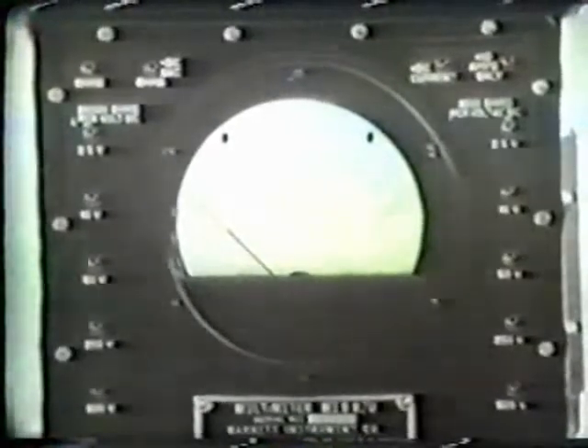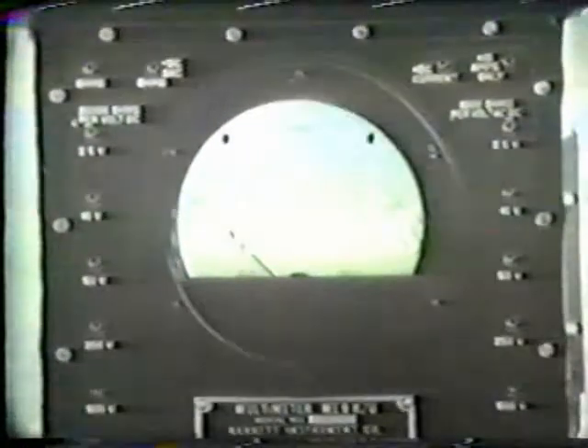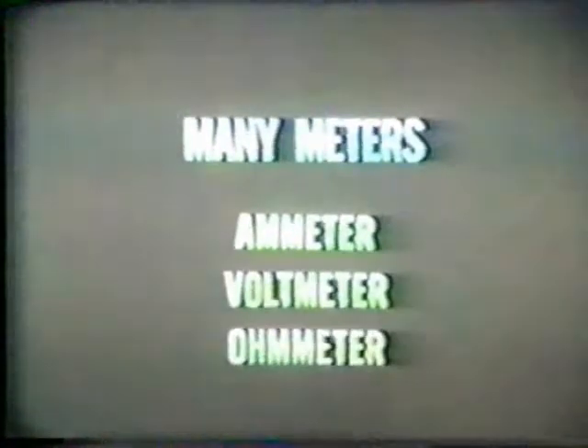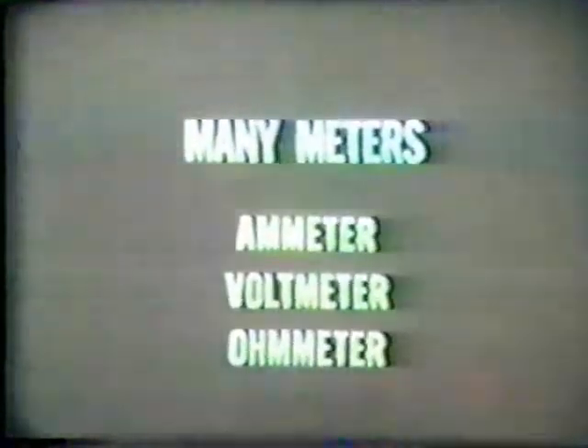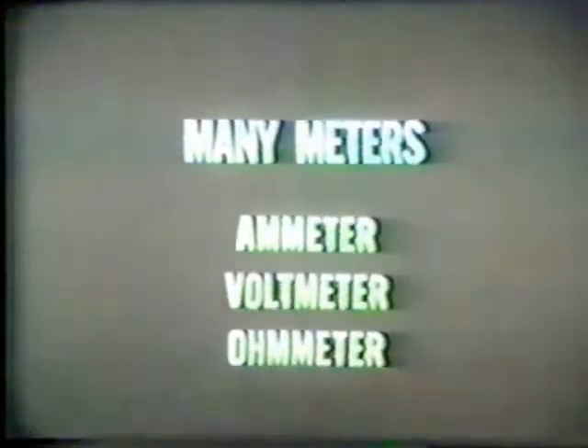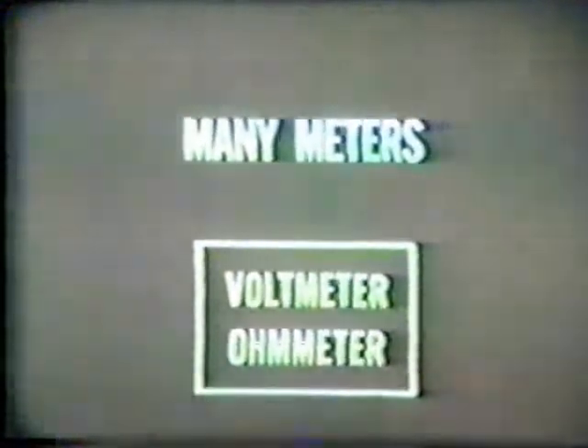A multimeter can do everything a jumper wire and test light can, as well as providing the extra sensitivity required for some electronic and instrument circuit testing. A multimeter looks quite complicated, but it is not difficult to learn to use one. Multi means many, and a multimeter is actually many meters in one. The multimeter which you will be using contains an ammeter, a voltmeter, and an ohm meter. Ammeters are not used in electrical troubleshooting, so we will not deal with them at this time. Voltmeters and ohm meters are very useful, and you must know how to set up the multimeter for either of these two functions.